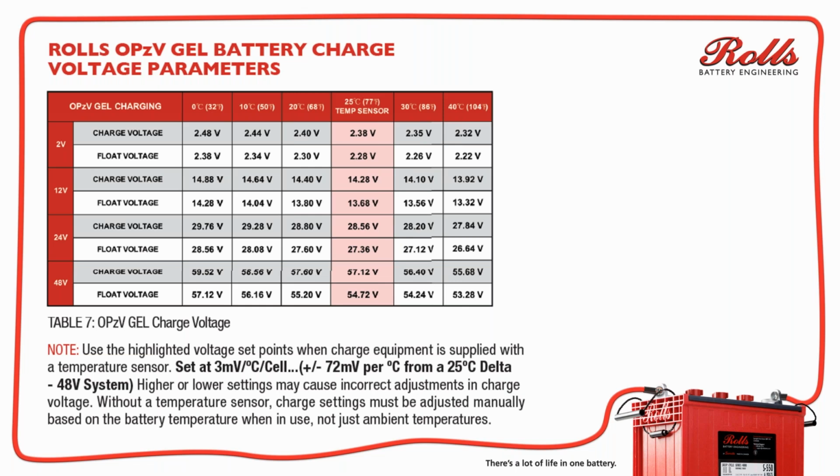Maybe we were having the lower charging settings then. It's okay, Mark, I get memory failures all the time. Anyways, I'll have to go back and check those old webinars to see if it actually does say that, because who knows, maybe I said that and it was some bad information. But typically when you get to the absorption voltage on a non-NAM battery, you're only about 80% state of charge.